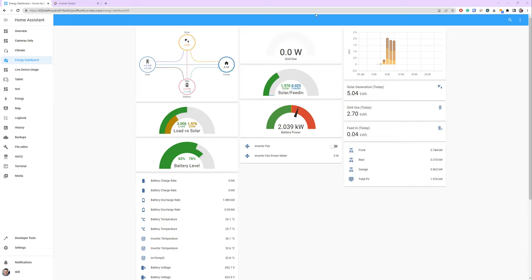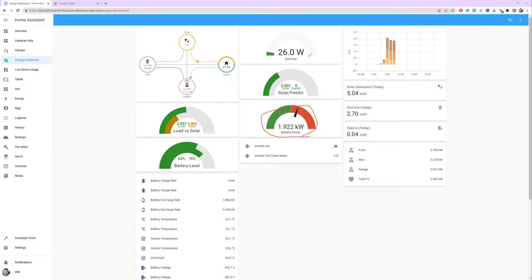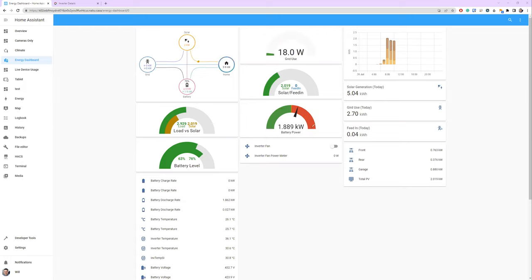Okay, so we're now taking from the battery. The grid didn't jump quite as much as what I'd expect. Sometimes you'll see several kilowatts jump immediately on the grid and then become balanced by the battery, because the battery does take some time to respond.